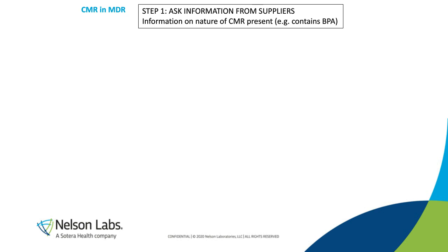So the first step in any CMR evaluation when you're looking to fulfill this for your MDR submissions should be going back to your suppliers. Your suppliers should have this information. They should be able to tell you that my material doesn't have more than this list of CMRs by percent. I do want to warn you though, having done this now for a couple of years with many of our clients, this isn't a foolproof approach, and you have to base your approach on how much trust you want to put in your suppliers versus how much you want to find out for yourself.